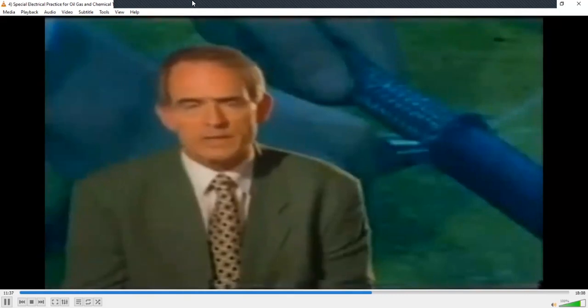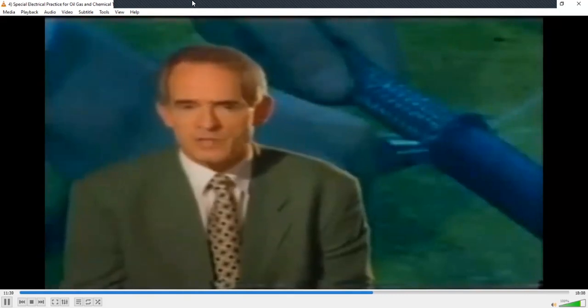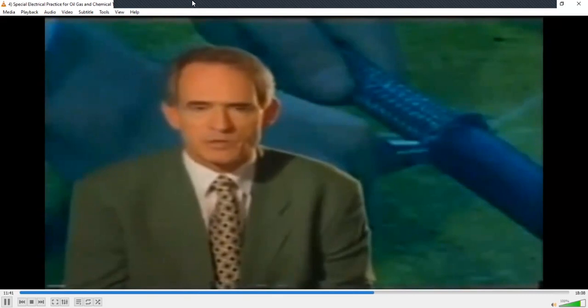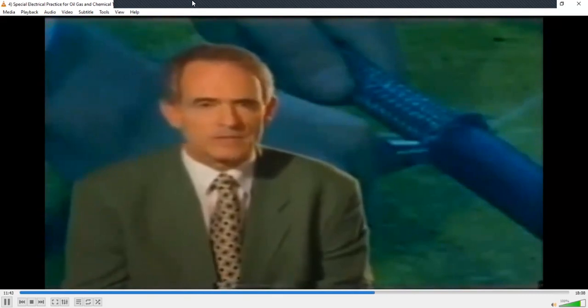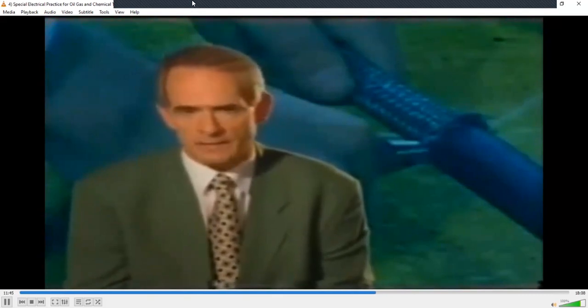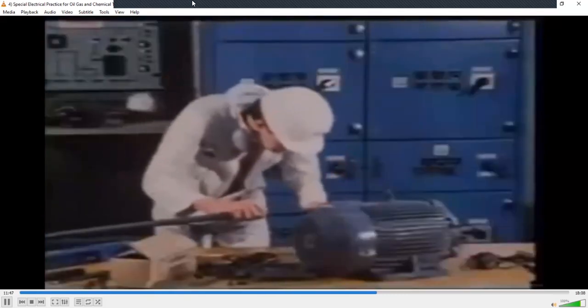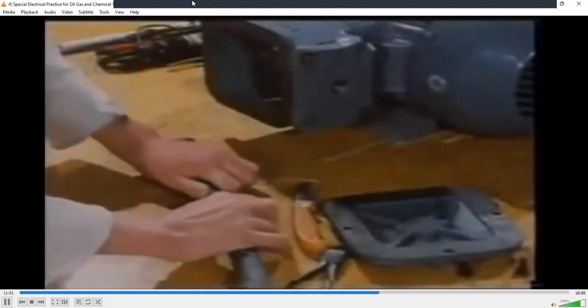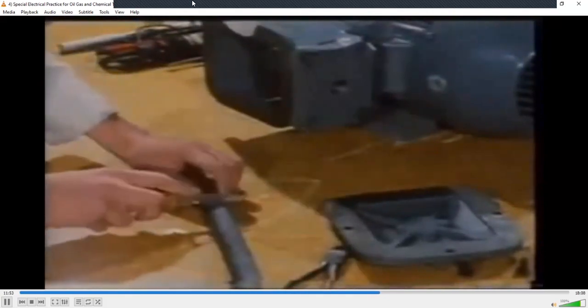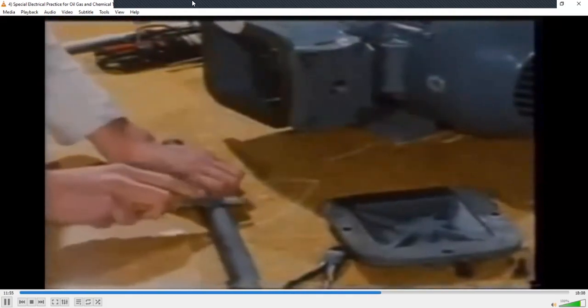When a cable run is laid to a flame-proof motor, special attention must be given to the preparation of the cable end and fitting the special flame-proof gland onto the cable. Here, the required length of the outer sheath is stripped off to reveal the steel armouring. Allow plenty of time for this work and use sharp tools.